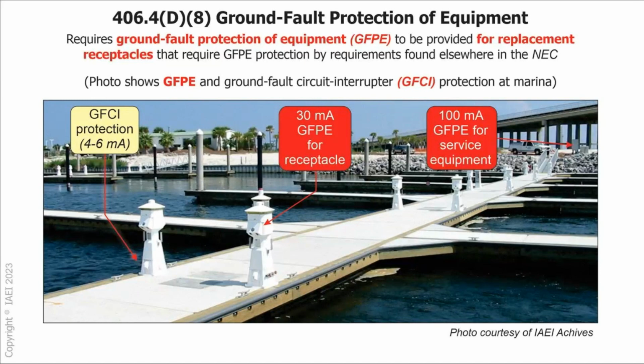Here's an example. A dock, 30 milliamp for protection of equipment. The difference for personnel is 4 to 6 milliamps. Okay, so the Class B GFI, 30 milliamp for equipment. Class A GFI, 4 to 6 milliamps allowed in the code. That's for people.